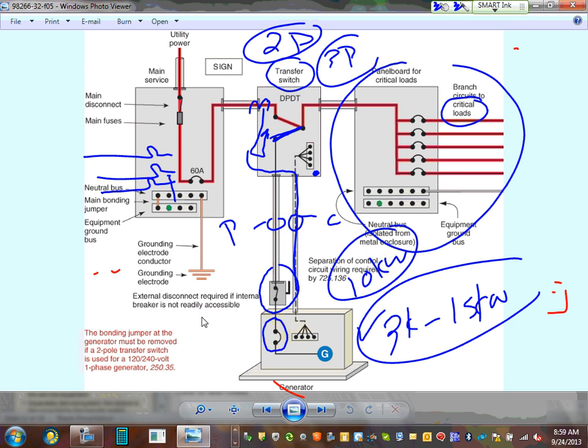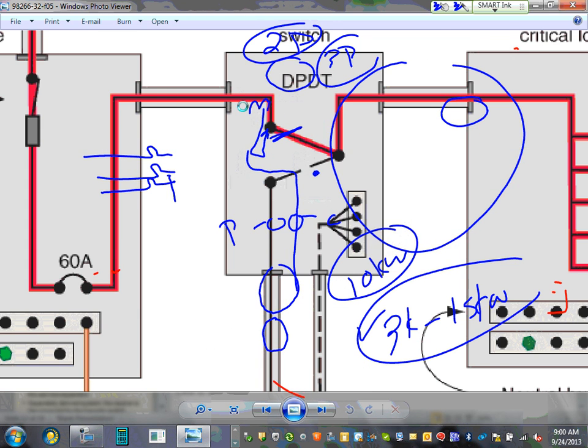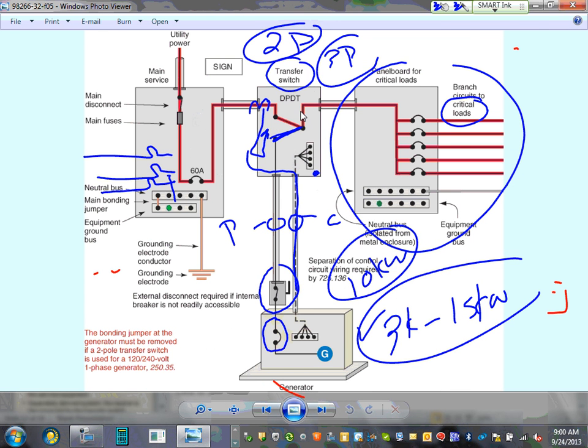So if you put in a 7.5 kW, you almost cover every load in your house. Almost. With a refrigerator and a dryer, don't turn your dryer and air conditioning on at the same time, or you might overload it. Any comments, guys? Any questions? That's the top of the line for a dwelling, a permanently installed wired generator like this. Now look what happens. Can you guys see the red? The power is coming in from the utility.